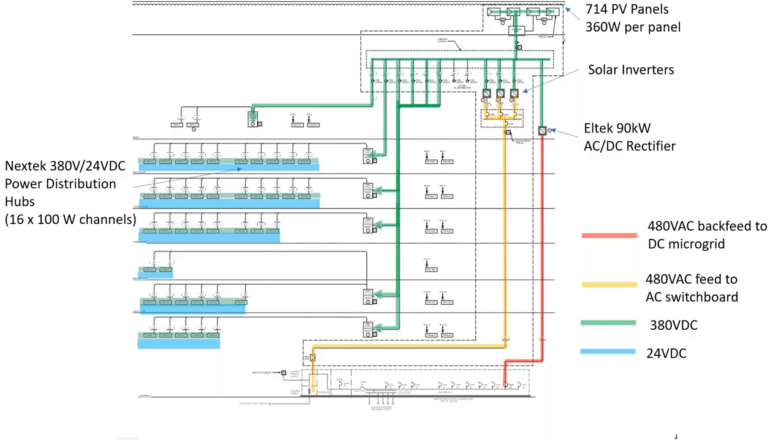When the power generated by PV is equal to the DC load, then the voltage will remain constant at the DC bus, and the PV will continue feeding the DC load. If the power consumed by the DC load is more than the generated PV power, the rectifier will convert the utility power from AC to DC, supplementing the remaining power required by the bus.